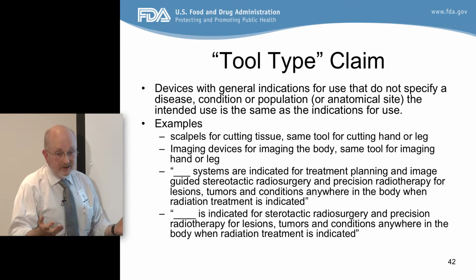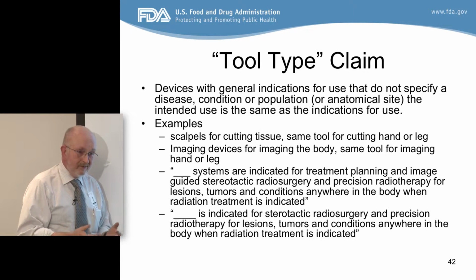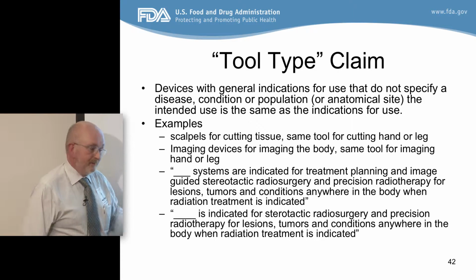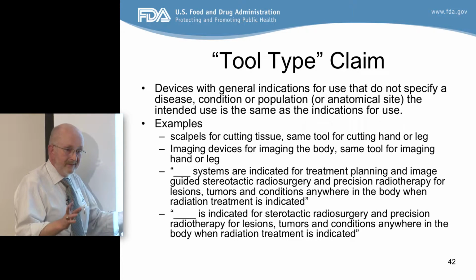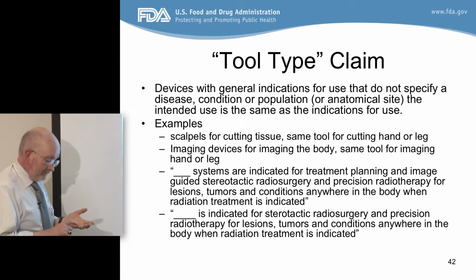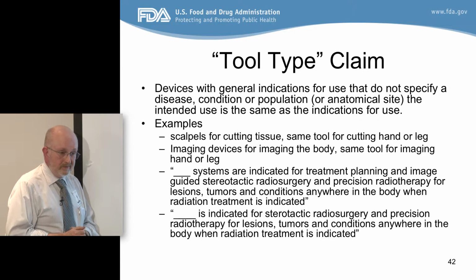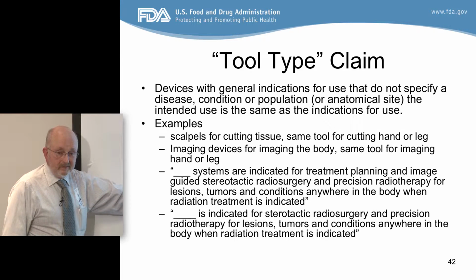So if you talk to Vic at NIH or somebody at ASCO, they may say that they disagree with what I'm saying. But so the 510K, it's a comparison. The tool claim is a general indication for use. These are reasonable claims.